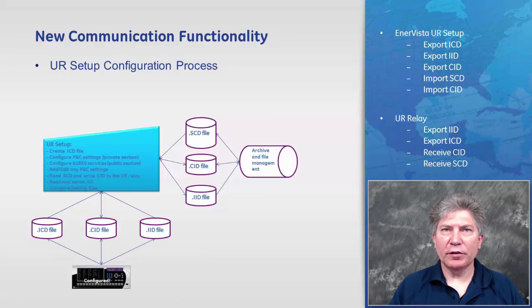From the online window of the EnerVista UR setup program, we can read the ICD and IID files from the UR relay. We can import SCD and CID files from the offline window. Each time a 61850 configuration is saved, it sends a CID file to the relay. The UR setup program can create ICD, IID, and CID files from the offline window to be used in station configuration language tools.